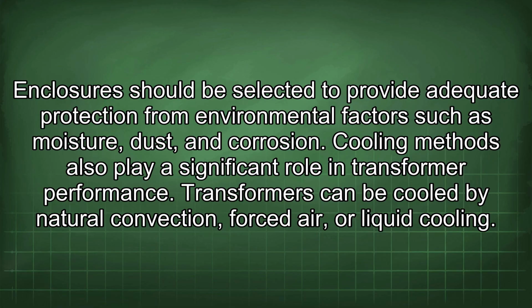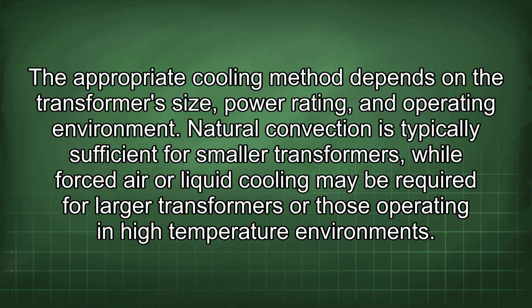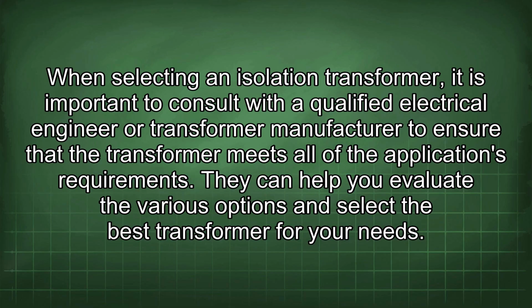Cooling methods also play a significant role in transformer performance. Transformers can be cooled by natural convection, forced air, or liquid cooling. The appropriate cooling method depends on the transformer size, power rating, and operating environment. Natural convection is typically sufficient for smaller transformers, while forced air or liquid cooling may be required for larger transformers or those operating in high-temperature environments. When selecting an isolation transformer, it is important to consult with a qualified electrical engineer or transformer manufacturer to ensure that the transformer meets all of the application's requirements. They can help you evaluate the various options and select the best transformer for your needs.